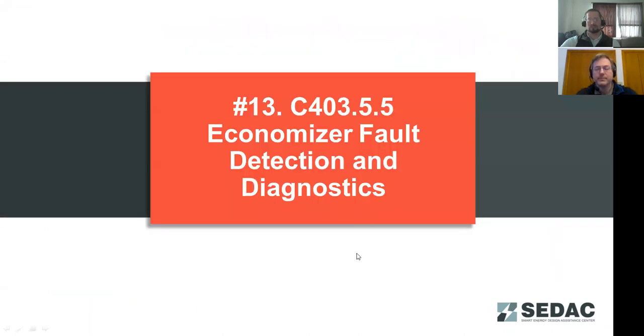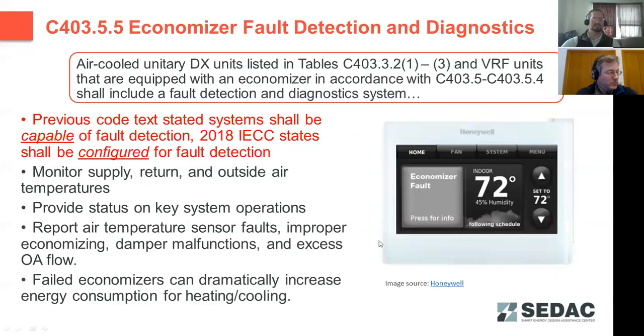So first we'll look at Economizer fault detection and diagnostics. For air-cooled unitary DX systems listed in the tables in the IECC, where they list efficiency requirements, and VRF units, they're required to comply with this Economizer fault detection and diagnostic requirement. The previous code, the 2015 IECC, simply stated that systems had to be capable of doing fault detection and diagnostics.